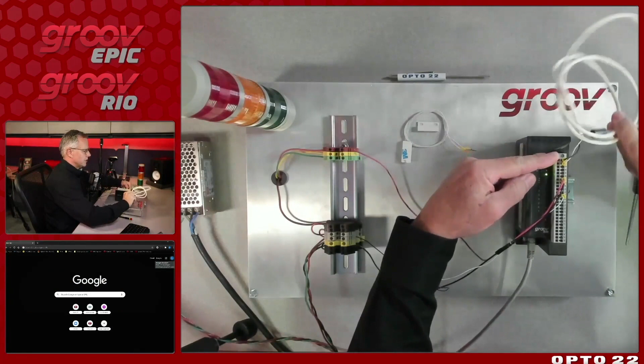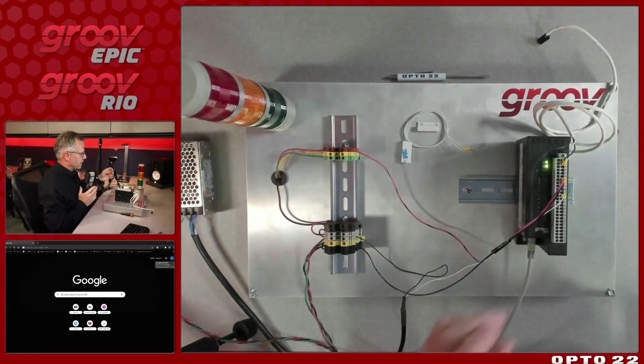I've got some other things wired up here too. I've got a couple of wires that go to my stack light, and this stack light will be able to turn on and off — I'll show you that in a moment. I've also got, if you look in my side screen, a column of water here, and inside is a temperature or level sensor. That level sensor is a 4 to 20 milliamp circuit, and it's wired up here to my Rio.